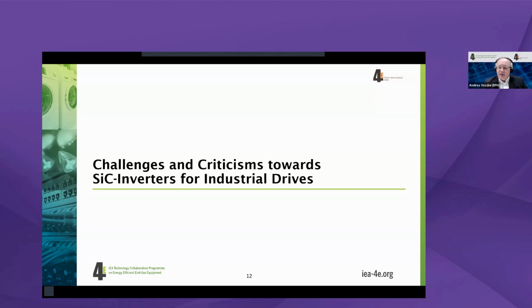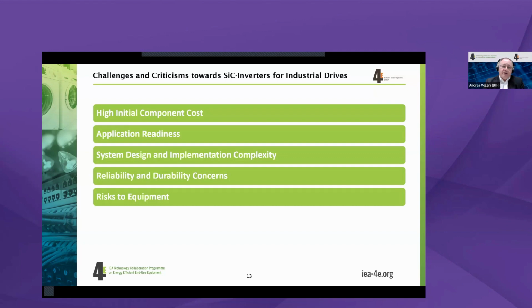And during a workshop organized by EMSA, we identified basically 5 reasons, which I'd like to present to you during this presentation. One is the high initial component cost, so we're talking about the higher cost of silicon carbide semiconductors compared to IGBT or silicon-based semiconductors. The other one is application readiness, so the availability, the volume, the number of different suppliers. System design and implementation complexity: as a new power component, it will also require different designs, not only on how to drive the power semiconductors, but also regarding cooling and filters. Then there are reliability and durability concerns. So we don't have the same experience as with silicon, and that's one of the bigger concerns here. And then the risk to equipment is also always cited as one of the hindrances.